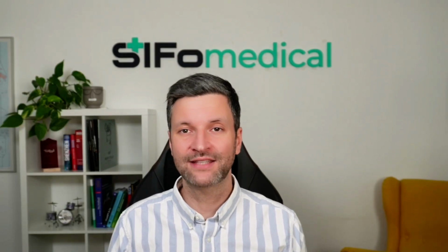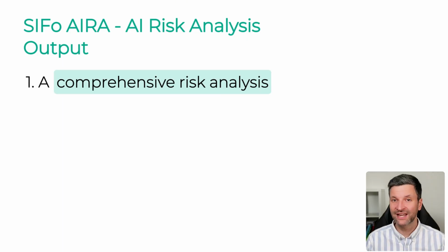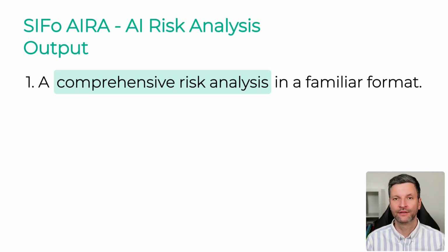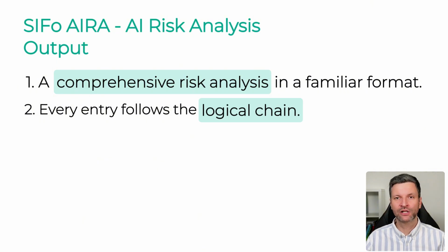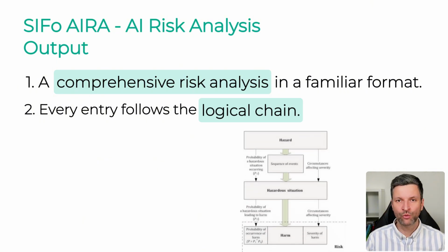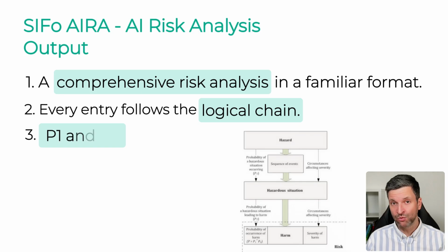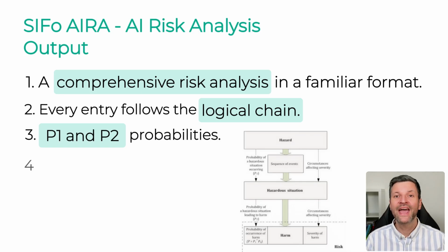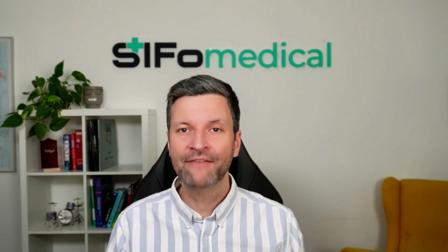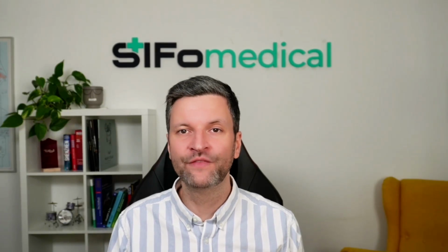What you get as output: a comprehensive risk analysis in a familiar format. Every entry follows the logical chain, hazard to hazardous situation to harm. You see P1 and P2 probabilities and severity classifications. Everything is a draft until you verify it.